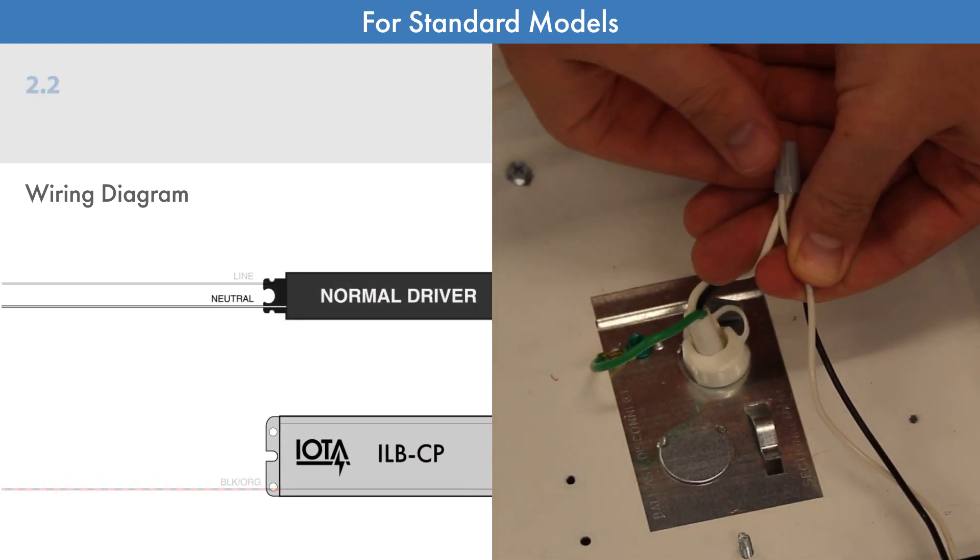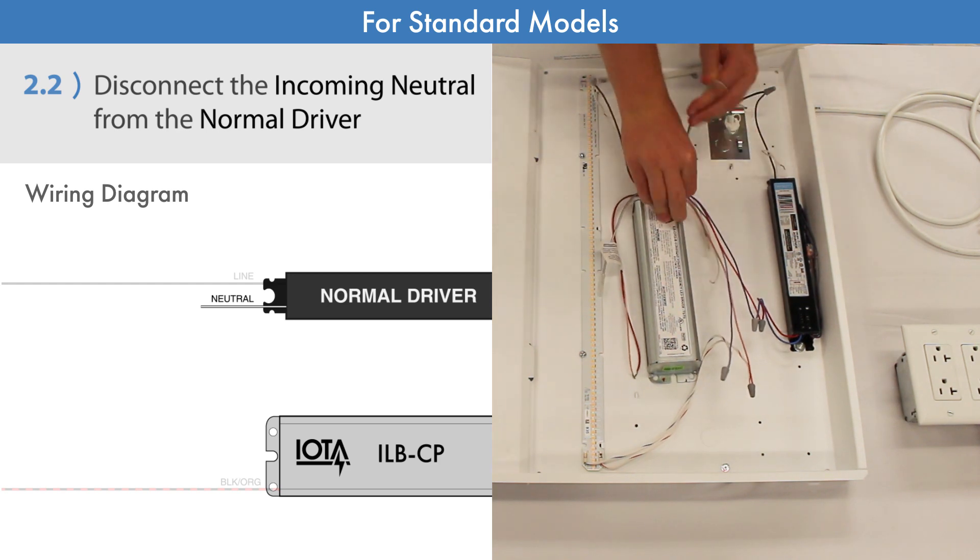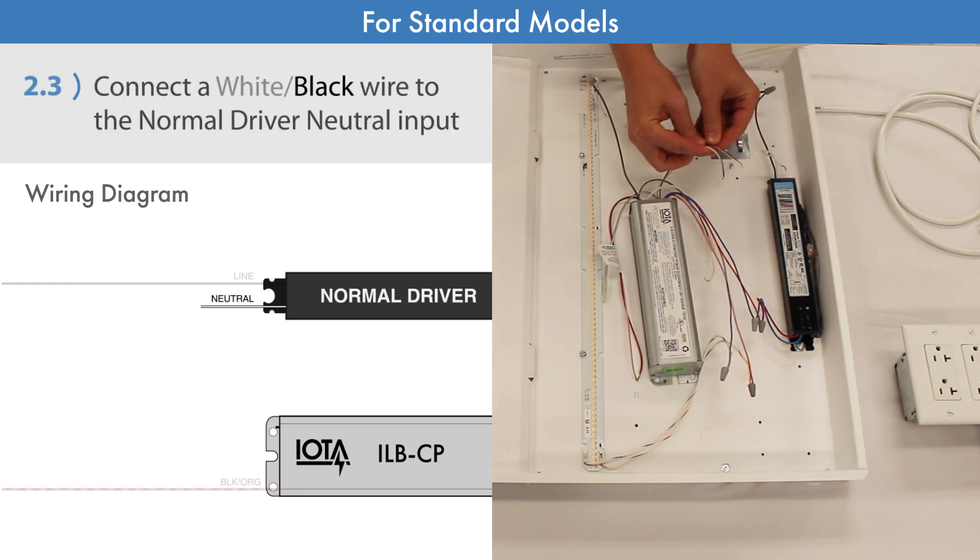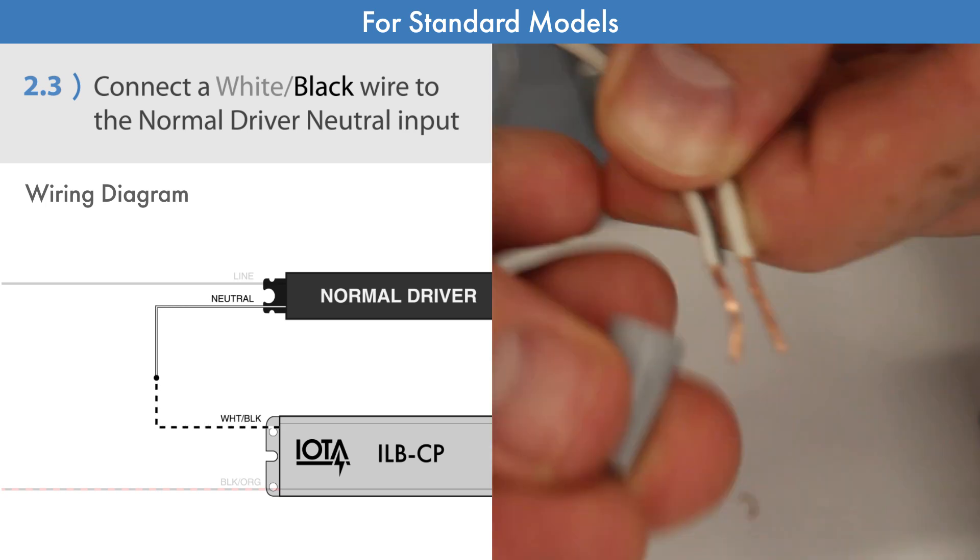Disconnect the incoming neutral wire from the normal driver. Then take one of the white-black wires from the ILB-CP, it doesn't matter which, and connect it to the normal driver's neutral input.